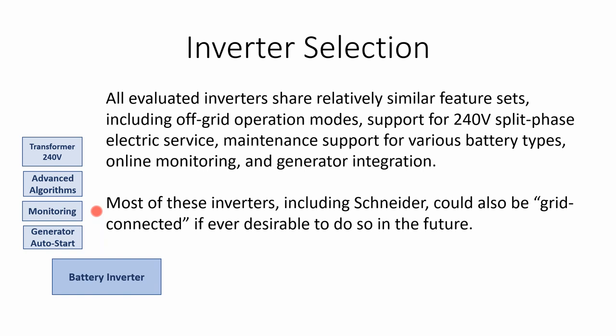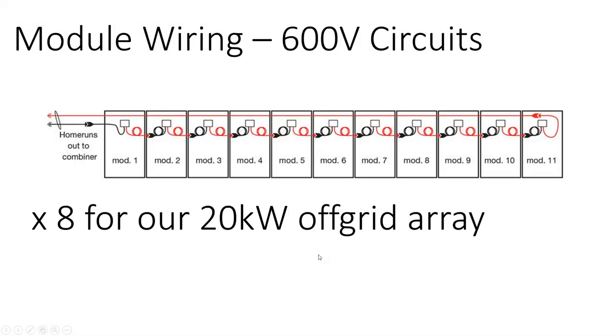You're also monitoring the temperature of the battery, which helps the inverter not pull too much power out of the battery. And in fact, you'll get into additional specs on the battery where if you need to shed some circuits because you're drawing too much power, you can turn off auxiliary circuits. Likewise, there's features where if your batteries are at a full state of charge, you'll turn on certain circuits that might not otherwise come into play, so that you avoid overcharging your battery, or B, so that you can use the power that you might not otherwise use.